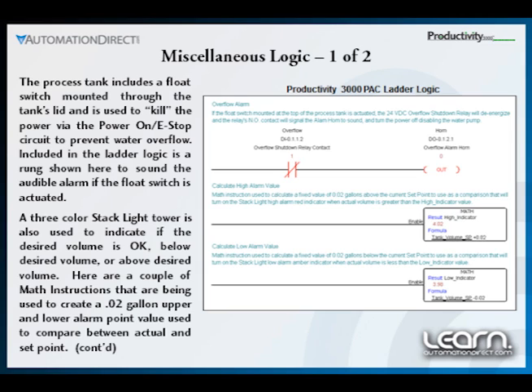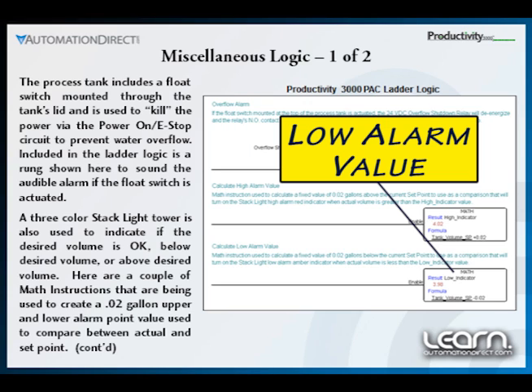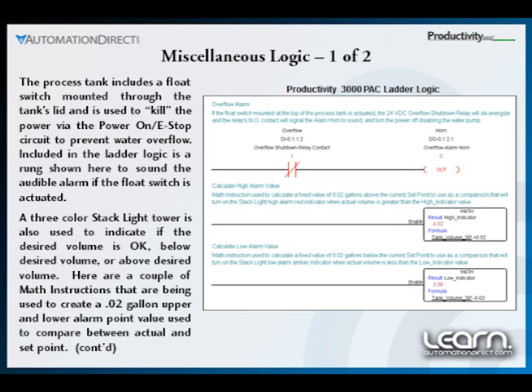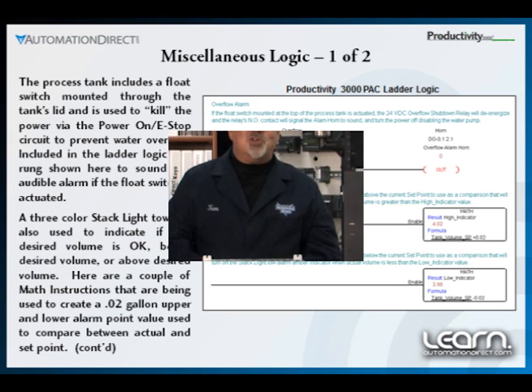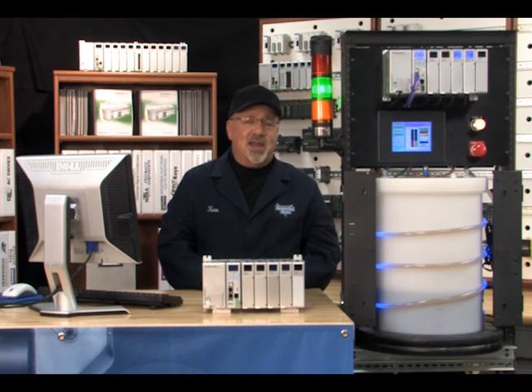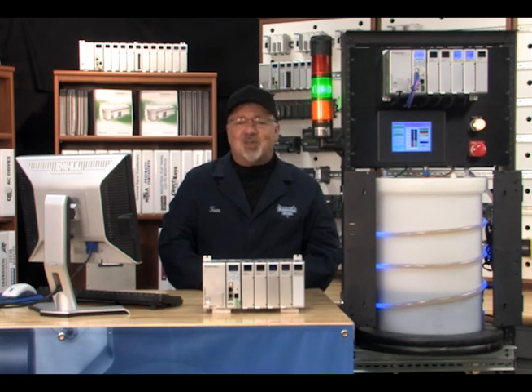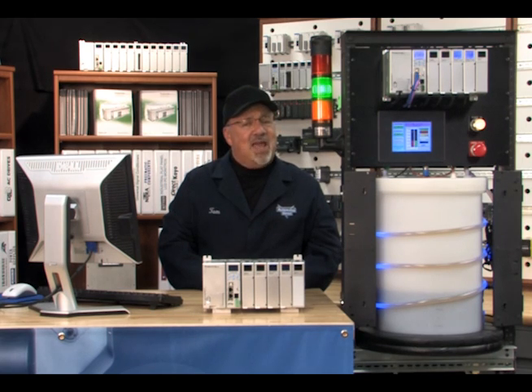Also shown on our miscellaneous logic are a couple of math instructions that are used to calculate a high alarm value and a low alarm value. A volume of 0.02 gallons is added to the current tank volume set point for the high alarm and subtracted from the set point for the low alarm. The results are used to control the three stack light indicators as seen in the next ladder logic explanation.